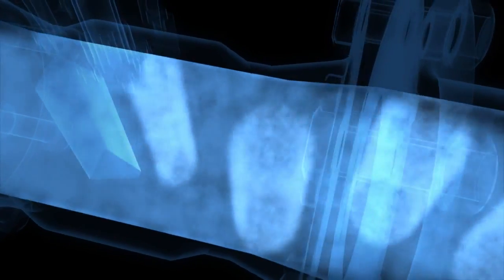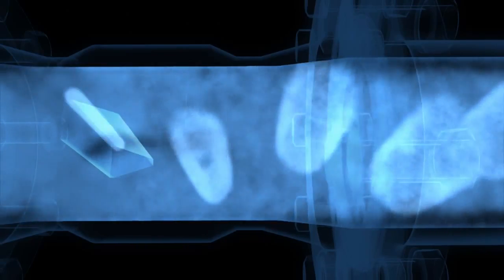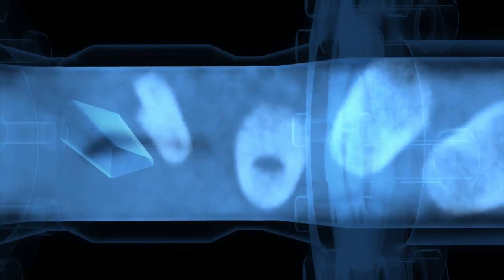As soon as the fluid starts to move and reaches a certain flow rate, vortices gradually appear downstream of the bluff body. These vortices are detached alternately on either side of the bluff body and are carried away by the flowing fluid. Zones of high or low pressure now appear downstream and thus create a phenomenon that is known as the Karman vortex street.